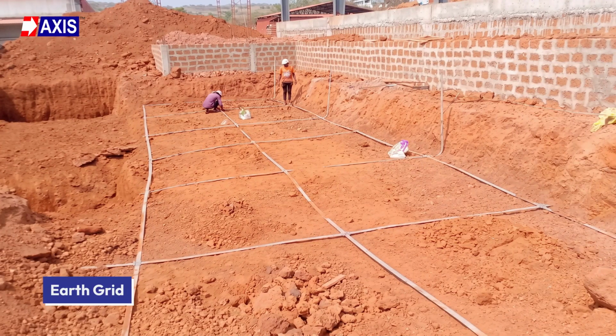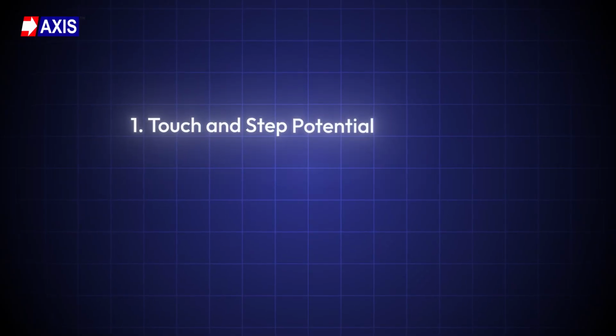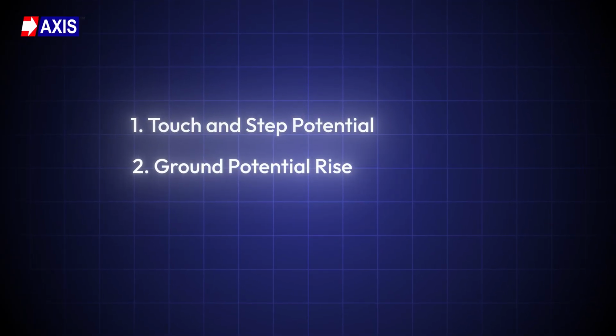Now, the substation earthing system is built around one core component, the earth grid. The earth grid is a network of conductive materials, typically copper or galvanized steel tapes, buried beneath the substation. It connects every piece of equipment to a common grounding point. It serves two purposes. First, it carries fault currents safely into the earth during fault conditions, preventing dangerous voltage rises within the substation. Secondly, it protects personnel by keeping all equipment at the same electrical potential, minimizing the risk of electric shock through touch and step potential, ground potential rise, and grid impedance.